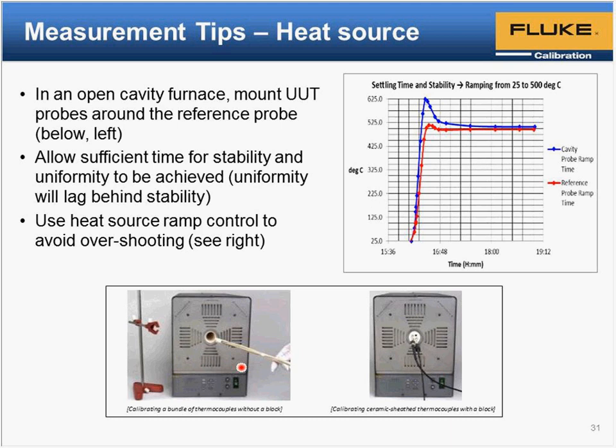Okay. Our question is from Zach. He says, do you include resolution uncertainty for the reference and the UUT? Good question. There are some very strong opinions out there that resolution should always be included. In this case, the resolution of the readout does go well beyond its specification, so it's covered by just using its specification, but there are readouts where the display resolution is directly linked to the accuracy of the instrument, or can be a limiting factor.